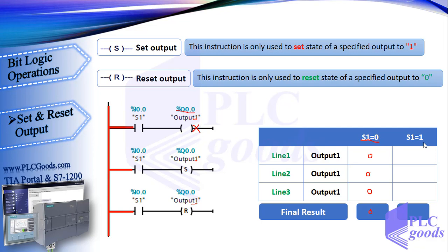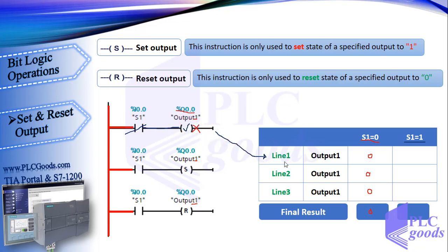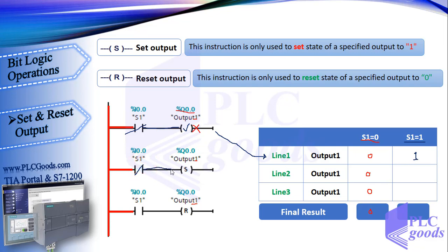At the second execution, suppose I0.0 is 1. So this contact with I0.0 address changes to close and passes virtual power. So CPU decides to turn this output on. But CPU won't do it until executing the whole program. Also pay attention, in the middle of executing the program, CPU doesn't see any change in its physical inputs. Based on the second line, CPU decides to set the output and finally in the last line resets the output.